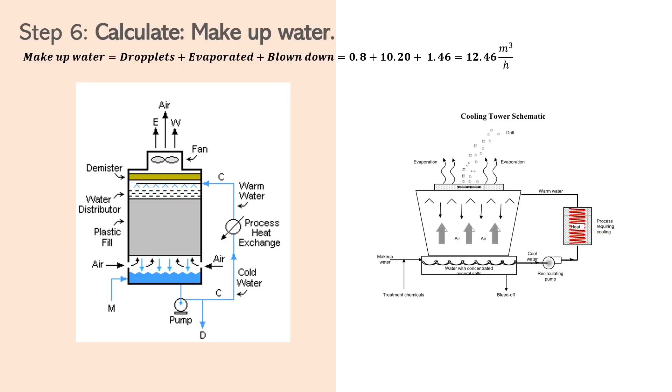The final step now is to get the makeup water. This is the water that will slowly enter our cooling tower to constantly make up for any losses that we are losing so that the water balances within our system. This will be made up of the water lost through evaporation, water lost through drifting, and water lost through blow down.